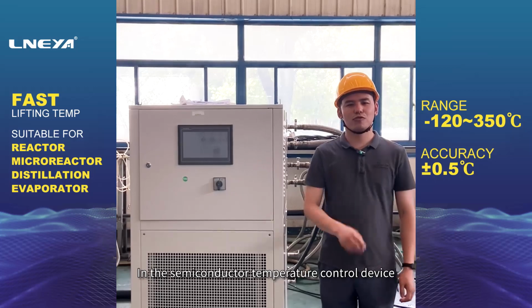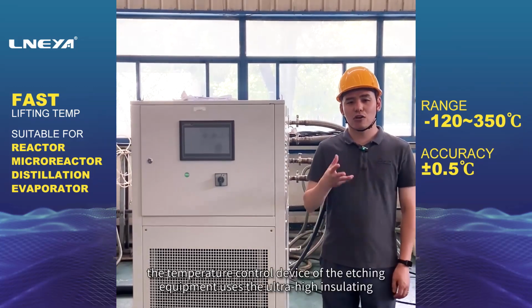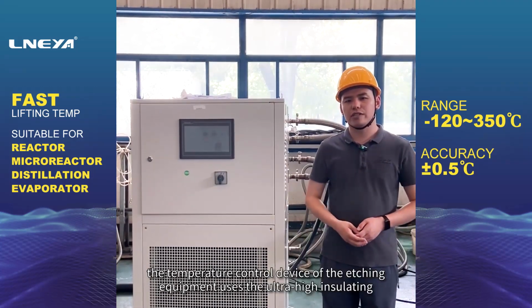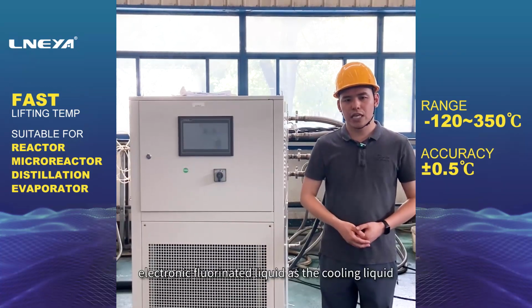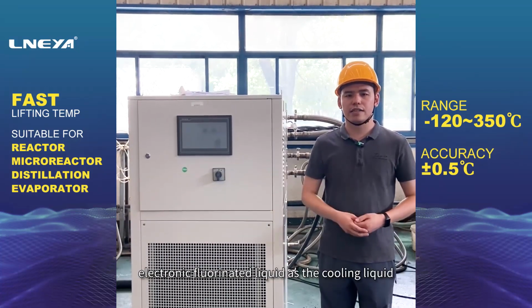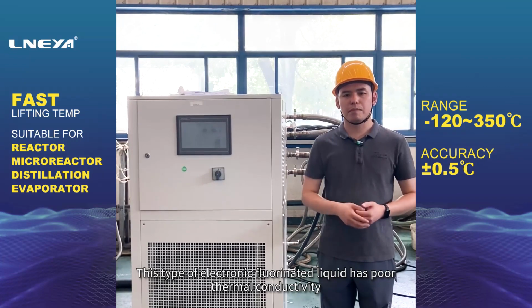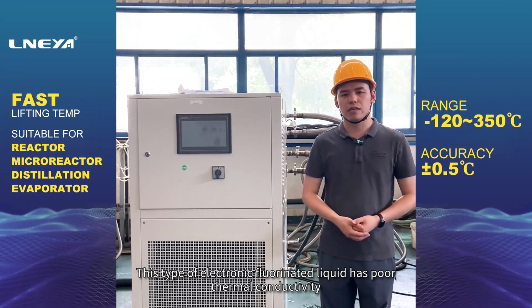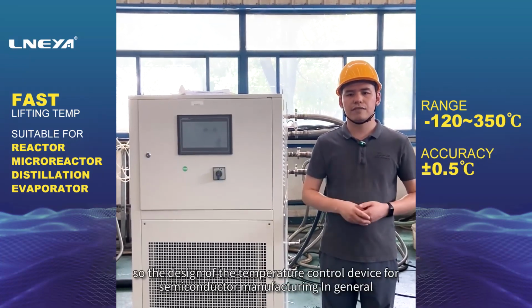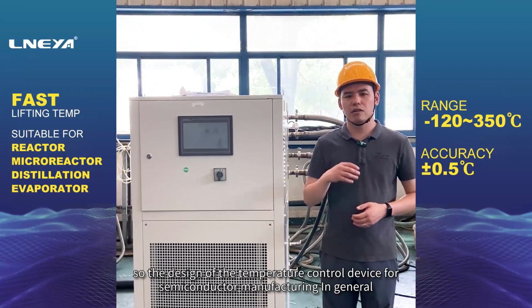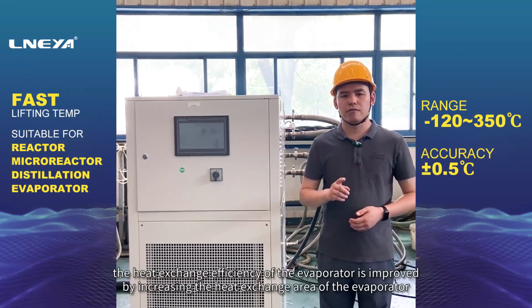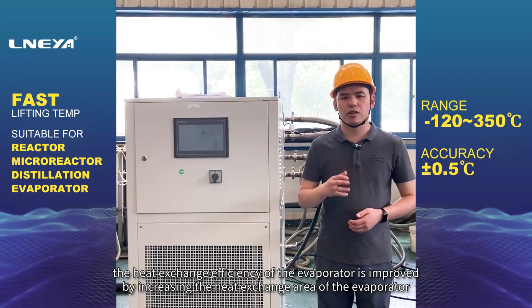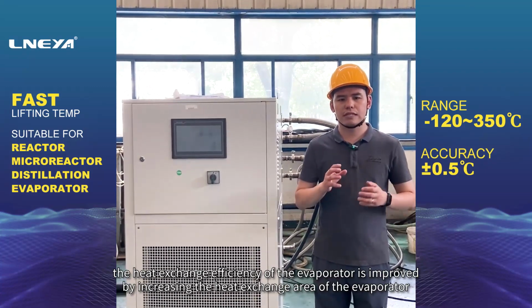In the semiconductor temperature control device, the temperature control device of the etching equipment uses ultra-high insulating electronic fluorinated liquid as the cooling liquid. This type of electronic fluorinated liquid has poor thermal conductivity, so in the design of temperature control devices for semiconductor manufacturing, the heat exchange efficiency of the evaporator is generally improved by increasing the heat exchange area of the evaporator.